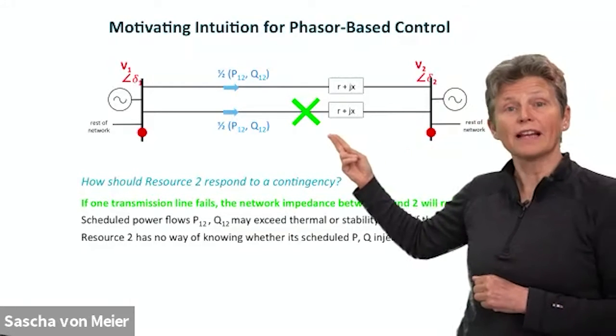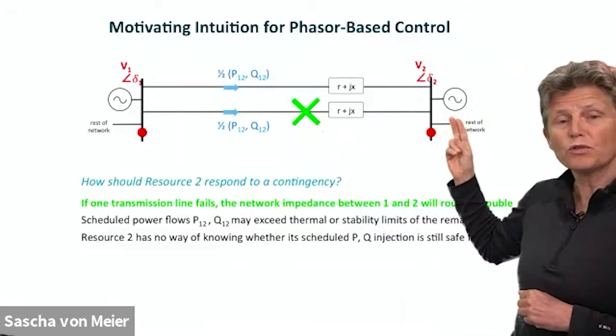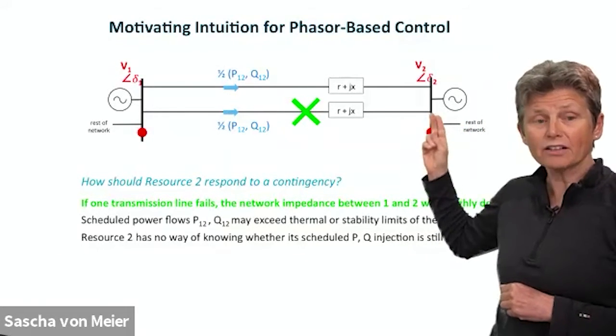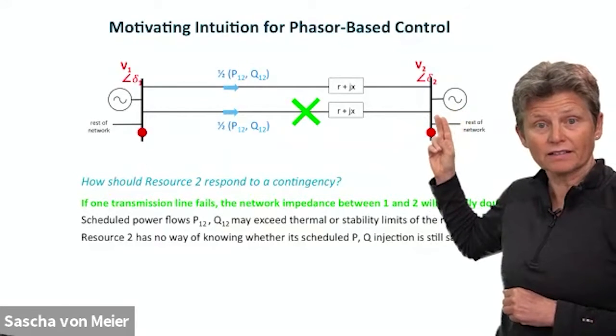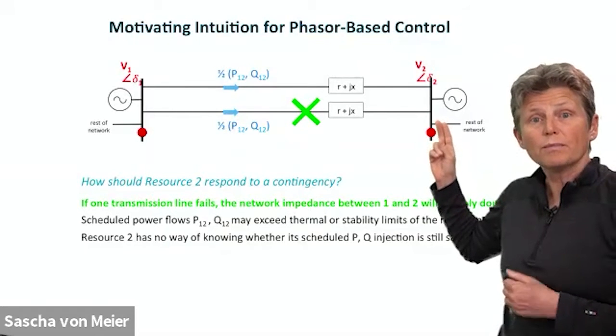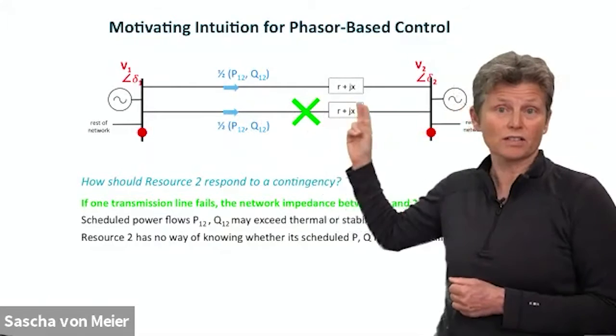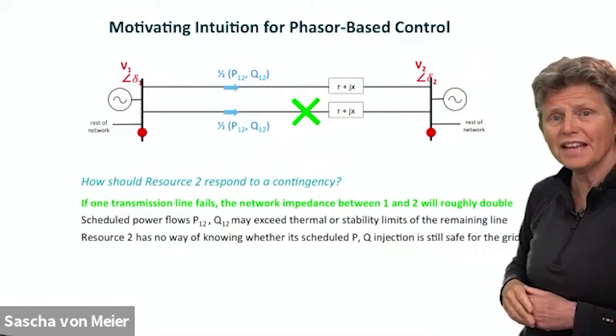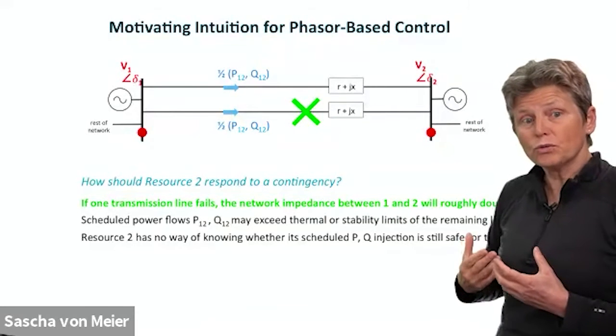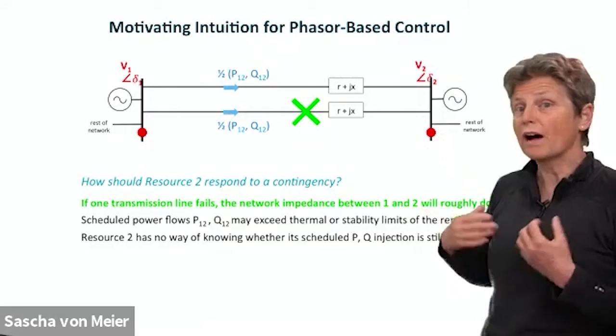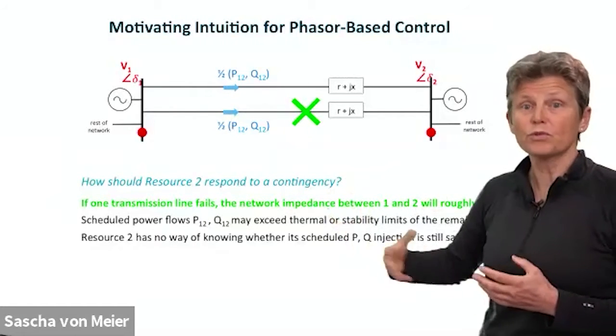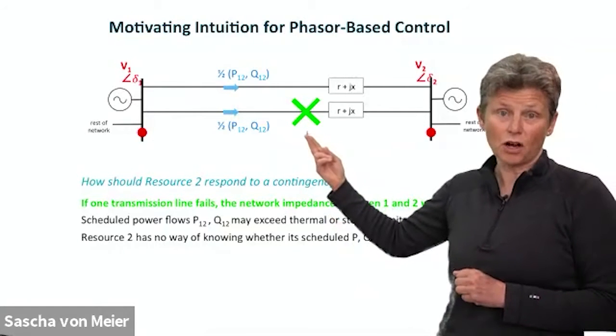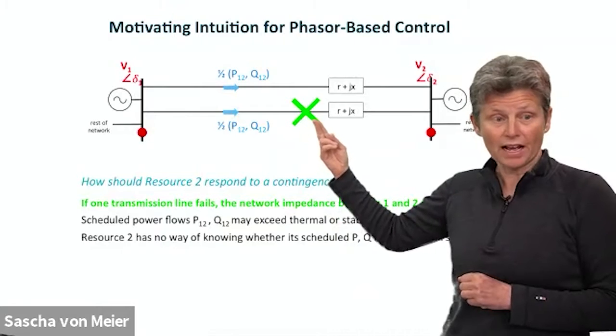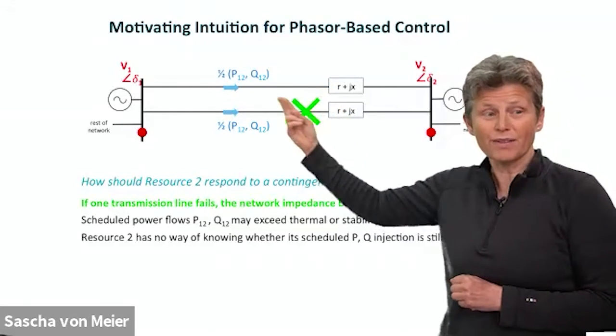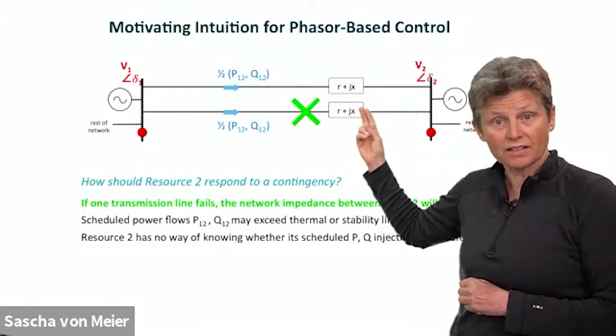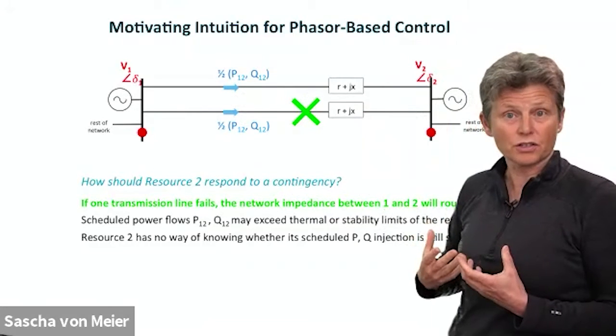Suppose that you have a transmission line outage. What you would really like to do is manage the power generated at node 2 to be responsive to any constraints that occur on this transmission line. In order to convey that information without phasor measurement, you would have to go through some other computation that recognizes: a transmission line went out, and now the remaining line on top has to carry the entire power flow from node 1 to node 2, which may be at risk of being overloaded. We're no longer in a secure state.